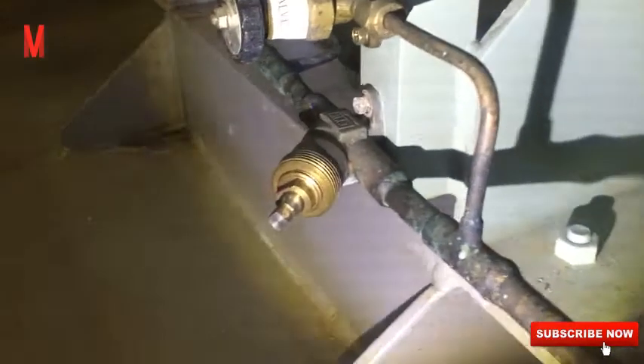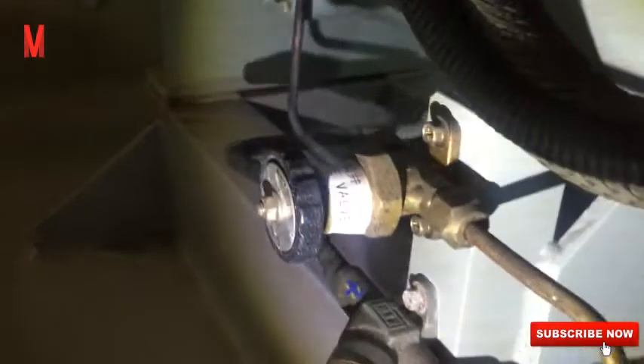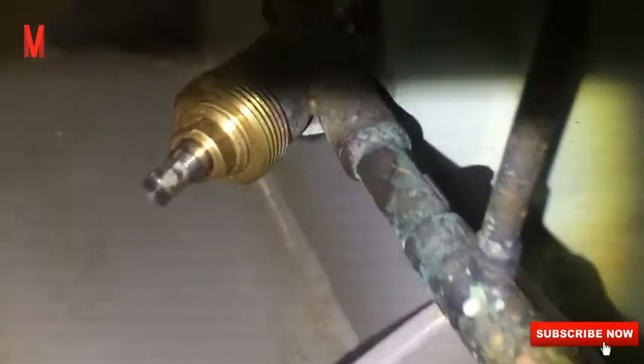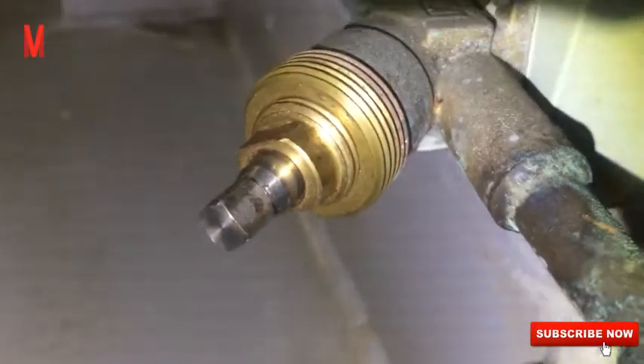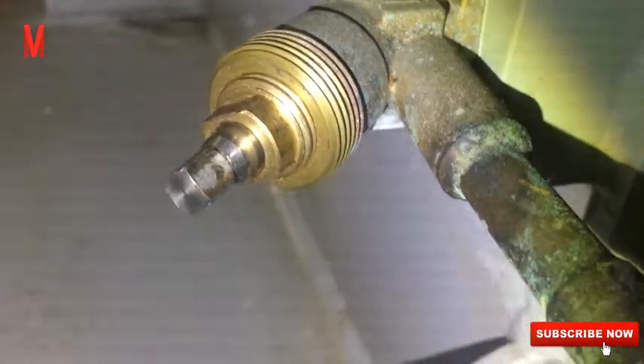The oil separator function is to separate the refrigerating machine oil, dahil may machine oil sa loob ng compressor. So this machine oil provides lubrication of the reciprocating compressor. So this separates the refrigerating machine oil, which is discharged together with the gas refrigerant in the compressor, and automatically returns the oil to the compressor. So this is very important, the oil separator.